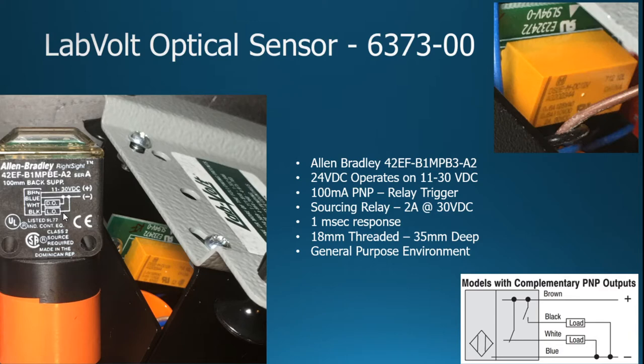Now in this case, we're actually not going to use the normally open, normally closed on the sensor for our control system. However, it does put 100 milliamps out. We may need to trigger something that requires a higher amperage. And so what happens with this LabVolt component is it will be using that sensor to trigger a relay. The relay actually has the common already wired to the positive, as you can see down below. The positive will either trigger that white or black and is showing the load in the bottom right hand corner there.